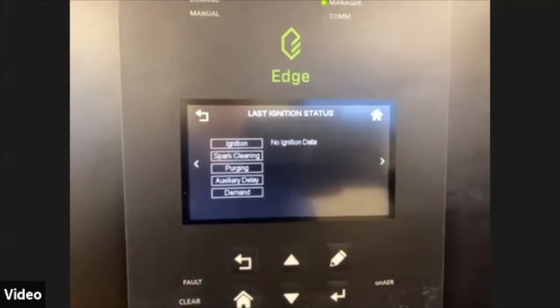The last screen will give you the last ignition status. This is the screen that'll come up as the boiler is going through ignition, and it'll populate each of those squares and tell you the timing and what's going on at each point. And once the boiler fires, this screen stores that information until the next firing sequence. So if you come in and the boiler's in alarm, you can come to the screen and see what happened during the ignition sequence and use that to help troubleshoot.